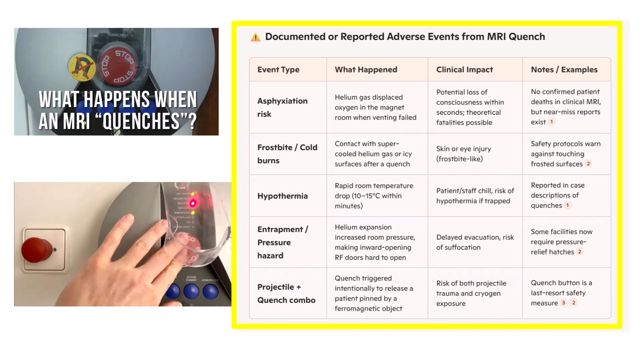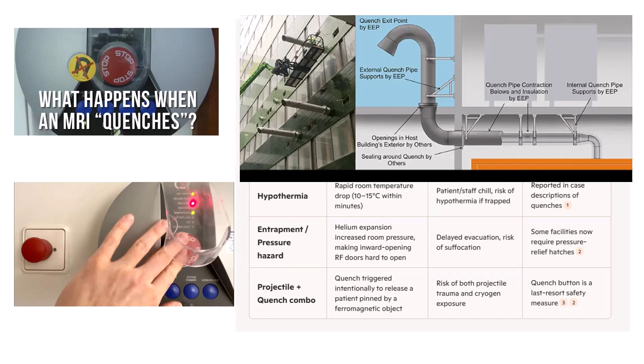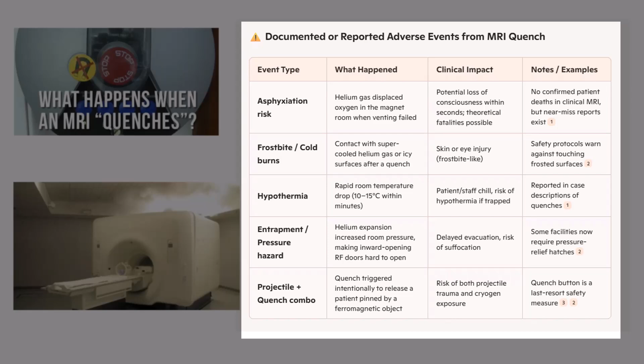A quench is essentially the magnet's emergency shutdown, a sudden collapse of superconductivity that vents helium gas. It's rare, but when it happens, the risks shift from radiation or magnetism to cryogen safety and oxygen displacement. That's why MRI rooms are equipped with quench pipes, oxygen monitors, and emergency evacuation protocols. Quenches are rare, but when venting fails, helium can suffocate, freeze, or trap patients. Proof that even the magnet's safety valve carries its own risk.